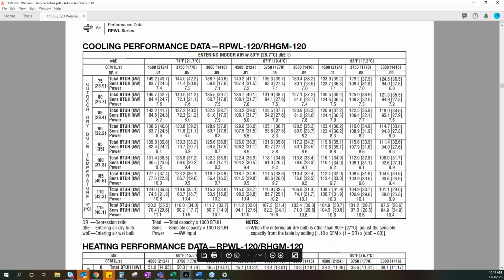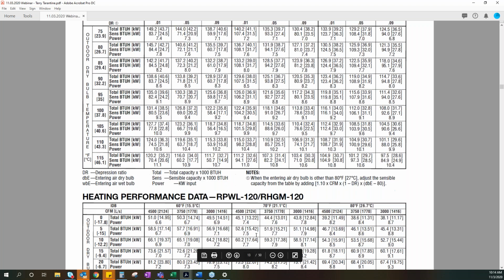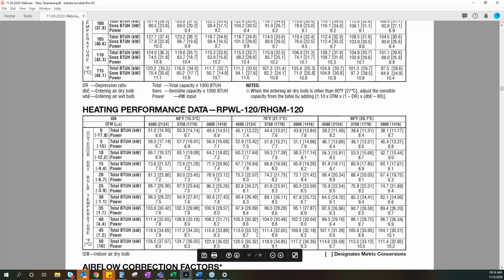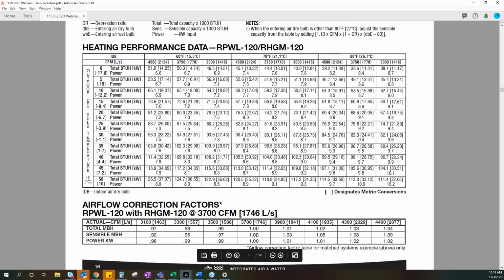Okay, here's the split system. We have the cooling data on top, and you can see the full cooling. If we scroll down just a little bit, you'll notice there isn't a lot of change when we go from a rooftop to a split system. This is an air handler and an outdoor condensing unit heat pump. Again, at 70 degrees and 5, we've gained a couple thousand BTUs. We're right around 52,000 BTUs of heat. Still not a lot, but better than we did on the package system.